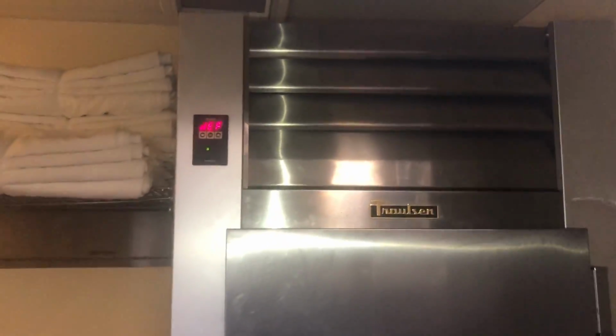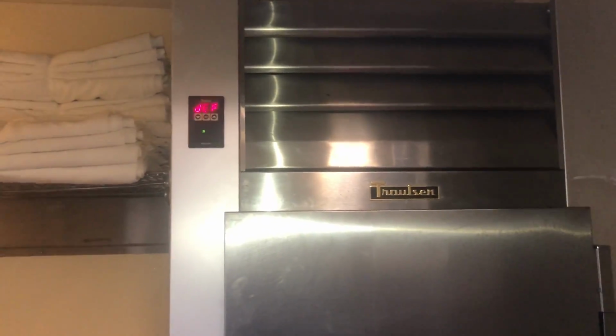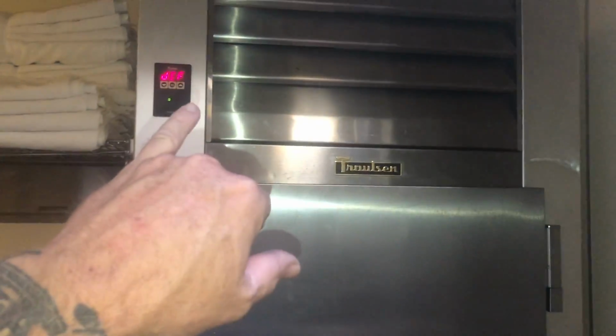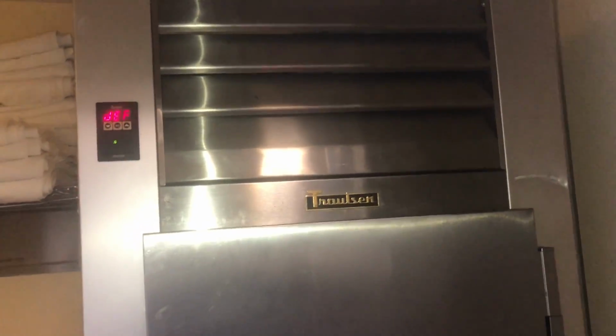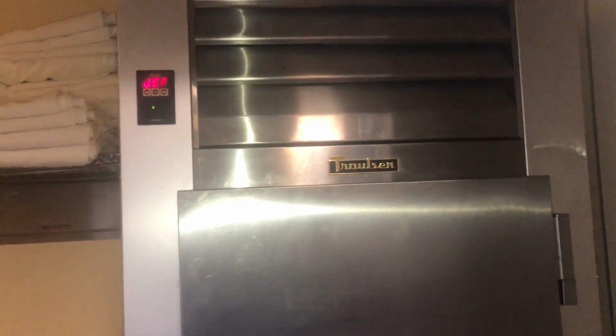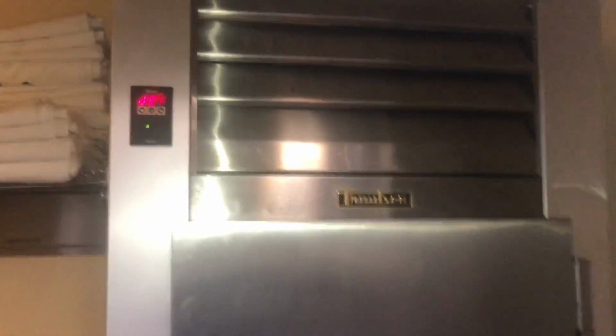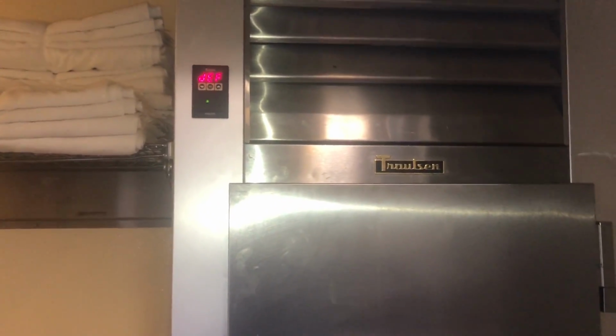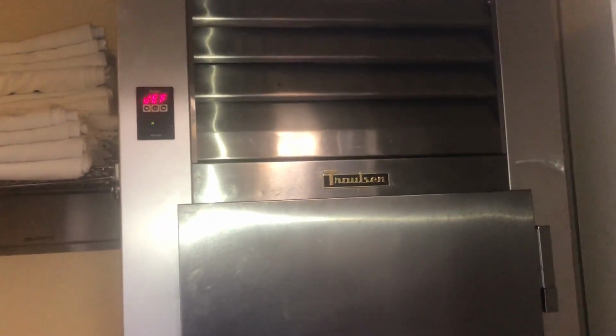Force the manual defrost, watch it go into defrost and come out. Compressor's off, check my amp draw, my heaters are good. We'll let it defrost, come out of defrost, and then we should be in good shape, using a harvested sensor whose ohms rating was close.